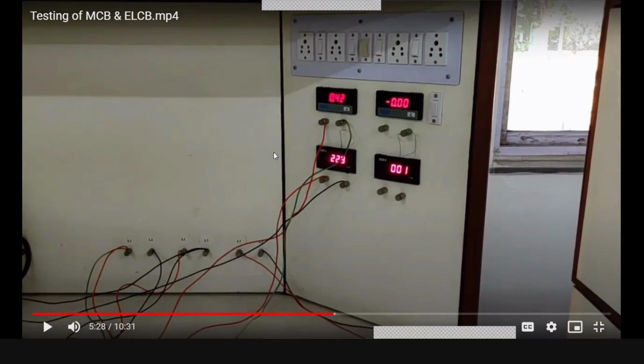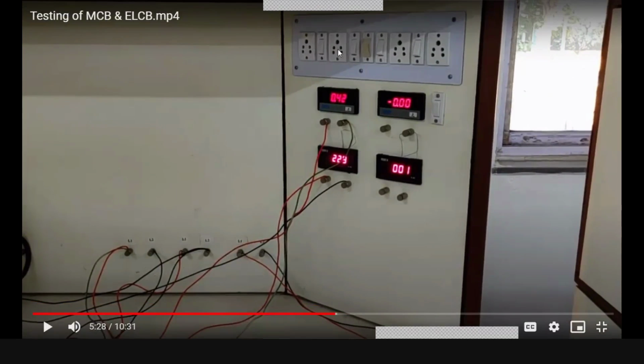Right now we have illuminated 4 lamps - we switch on 4 lamps, so the current is 0.42 at 230 volts. The 230 volt voltage we are giving to this circuit is fixed. Now if we increase the lamps, the current will increase. Up to 2 ampere the current is normal for the MCB since this is a 2 ampere rating MCB. Beyond 2 ampere, the MCB will consider it an overloading condition.